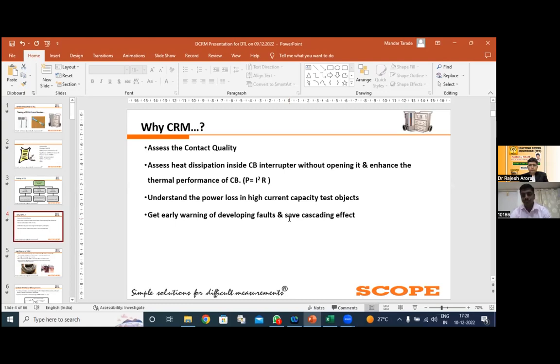So by assessing the contact quality with the help of this CRM, we can assess the contact quality. Second, we are supposed to check the contact resistance of the breaker. In the case of an EHV circuit breaker, the static contact resistance of the main contact is basically in the range of 32 to 40 micro ohm. If for any reason your contact resistance goes on increasing, as the resistance is a passive component, then the power loss is nothing but I square R.